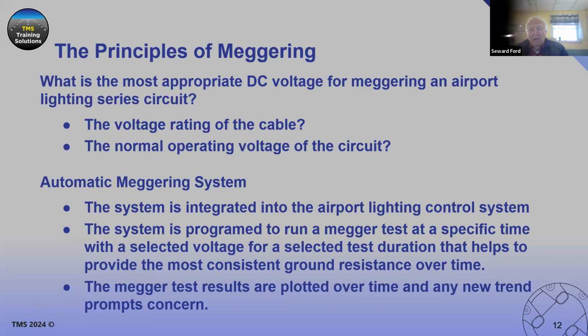We have 5,000 volt cable, but especially in the newer circuits, we have very few places on that circuit where there's ever even close to 5,000 volts. So if we use 1,000 volts, that's more conducive to the voltages we see there, and so we can keep an accurate record of what's happening with regard to the realm of the voltage that the circuit is operating at. And so now there's some instances where initially you test at a higher voltage. Keith, do you want to mention a little bit there?